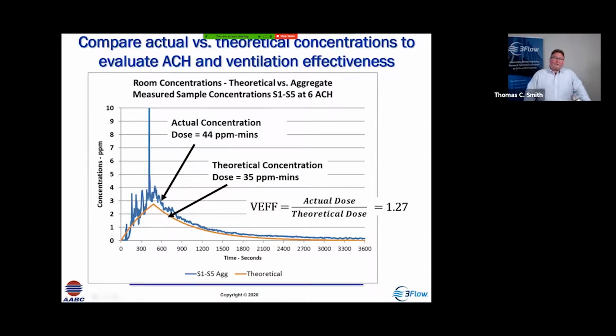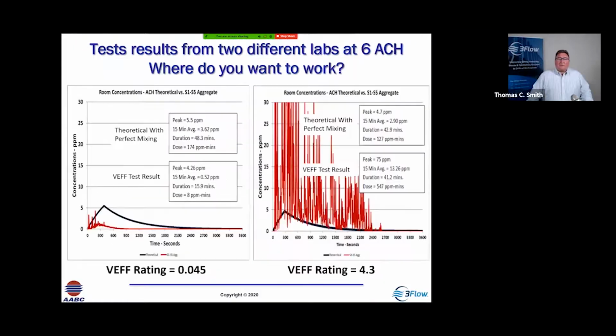If the VEFF factor, which is the ratio between the actual concentrations to the theoretical concentrations, is greater than 1, that means the room is compromised. It's not working effectively. If it's less than 1, it's working well. So here's two examples. Two labs working at the same air change rate. The one on the left has a VEFF factor of 0.04. You can see the red here is the actual concentrations versus the black is theoretical. The dose is 174 theoretical, the actual is 8.